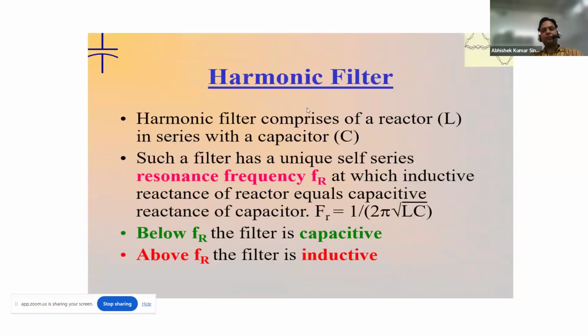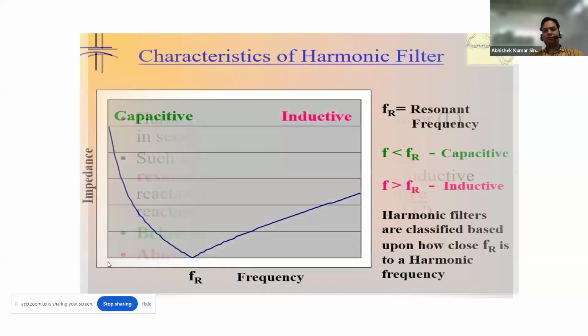Now we are looking at harmonic filters. For harmonic filters, we have already studied that there is an FR. A filter has a unique self series resonance frequency, which is FR. Below that FR, the filter will act as capacitive, and above the FR, the filter will act as inductive. So if there is a high frequency, it will act as inductive. If there is a low frequency, it will act as capacitive. This you can see.